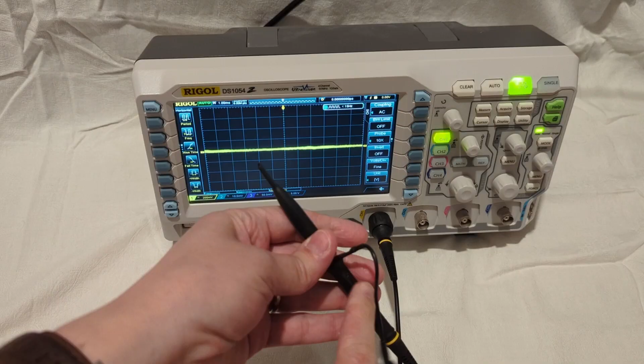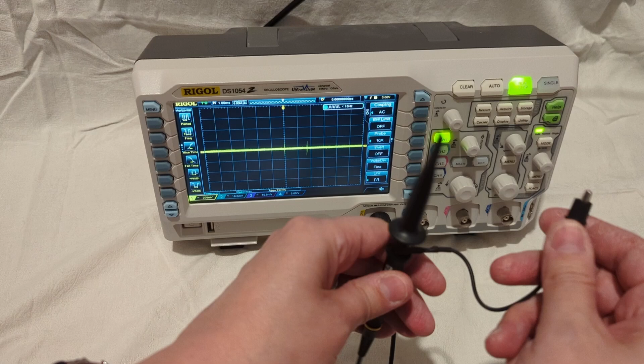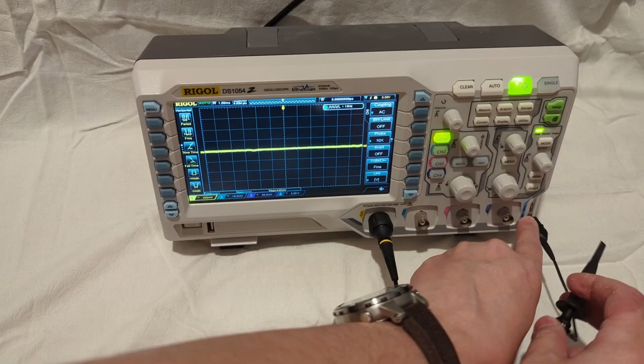In order to compensate a probe, the first thing you need to do is to have a consistent signal to hook this up to. Fortunately, the majority of scopes, in fact, every scope I've ever used, has a compensation signal set up already. So you just hook up the ground to the bottom tab over here, and the end of your witch's cap to the top signal there. And now you can see that I have a waveform showing up on my screen. If the signal is going off your screen vertically like this, then you can adjust it by turning this knob. You just need to make sure that you've selected channel 1, and then you can go in and adjust.